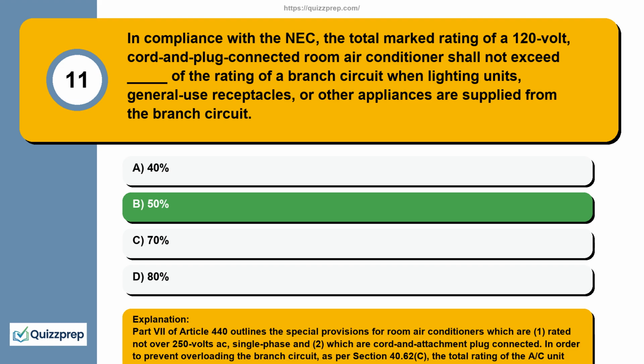Part 7 of Article 440 outlines the special provisions for room air conditioners which are 1. Rated not over 250 volts AC, single phase, and 2, which are cord-and attachment plug connected. In order to prevent overloading the branch circuit, as per Section 440.62 c, the total rating of the AC unit shall not exceed 50% of the rating of a branch circuit where lighting units, general use receptacles, or appliances are also supplied.